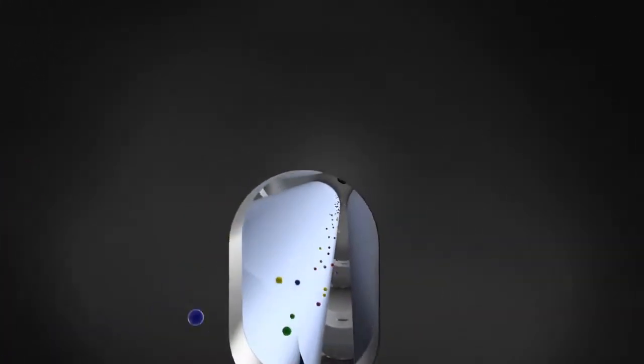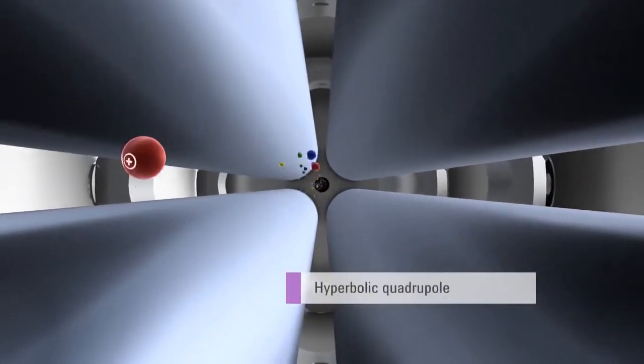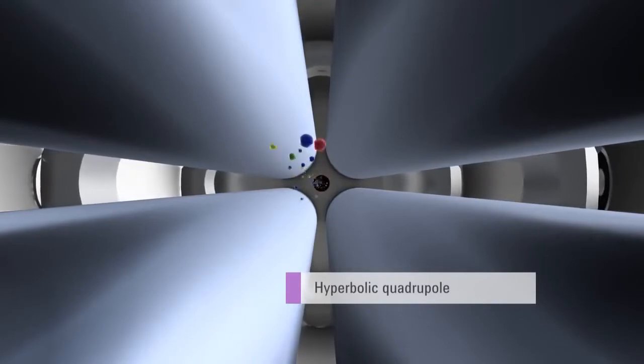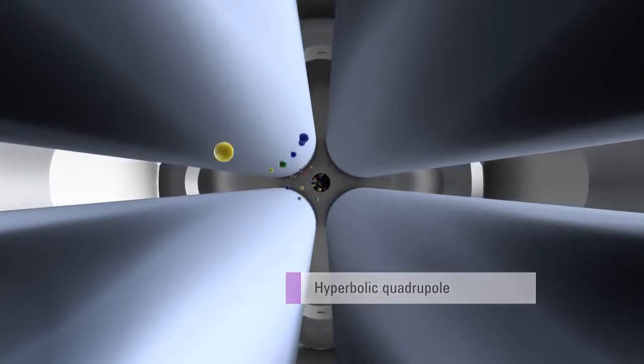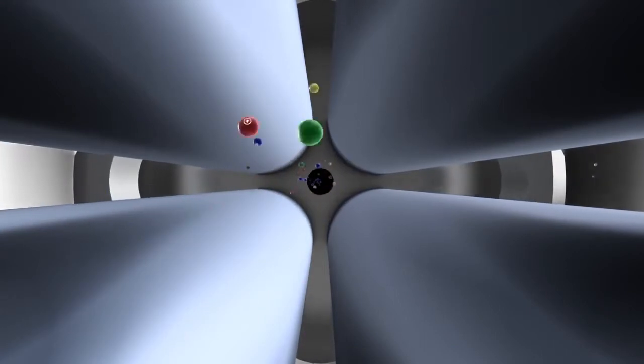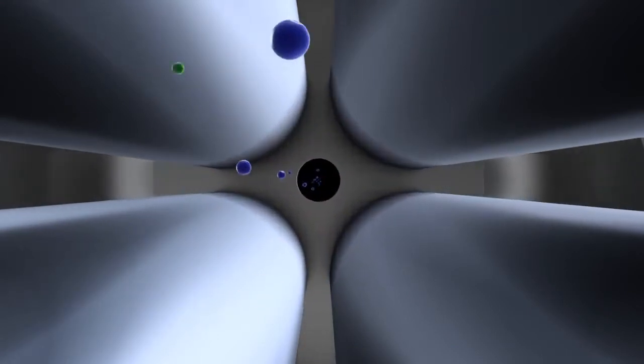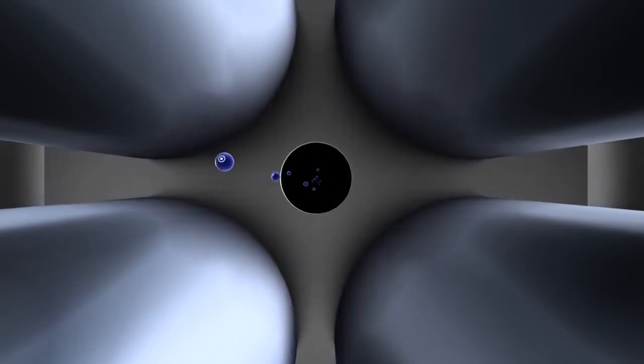From the collision reaction cell, the ions pass into the quadrupole mass analyzer, which separates ions based on their mass-to-charge ratio. The 7700 is unique in using a high-frequency 3 MHz hyperbolic quadrupole. These features combine to give improved peak separation and higher transmission, providing the 7700 with the best abundance sensitivity specification of any quadrupole ICP-MS.